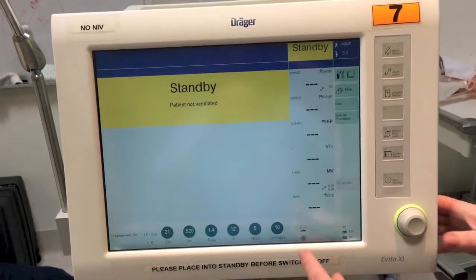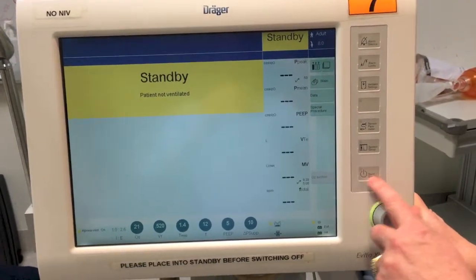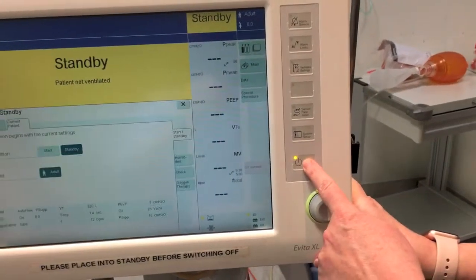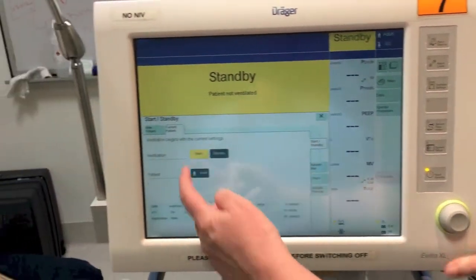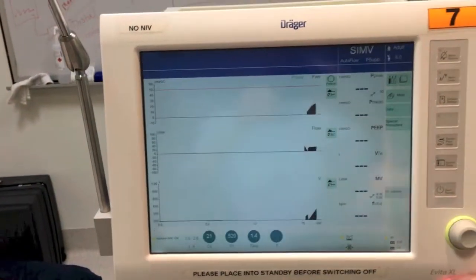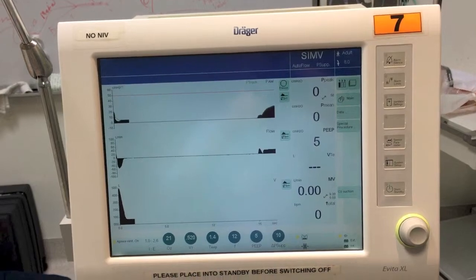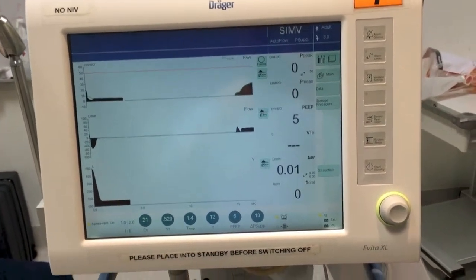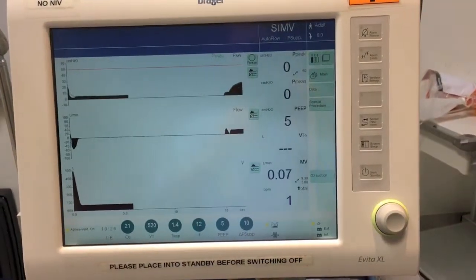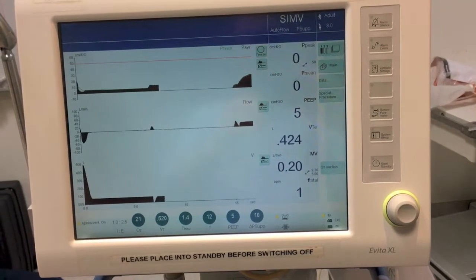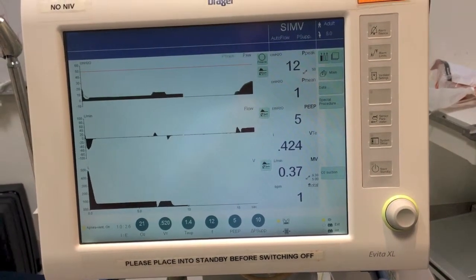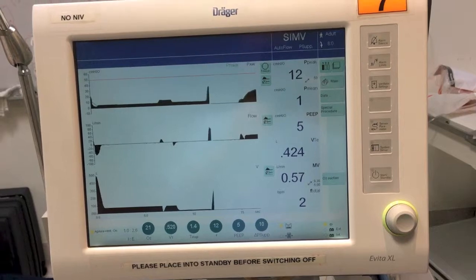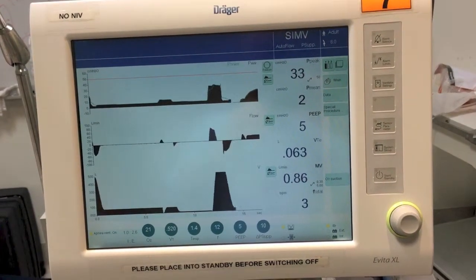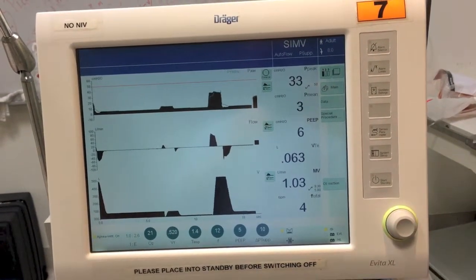So I'll close that now, and then we're going to take it out of standby. The standby button is just on the bottom here, and then we click start, click to confirm, and then your ventilator is auto cycling. It's attached to the test lung, which is just below the ventilator here, and you check that the ventilator circuit delivers the correct tidal volumes. If it didn't, it possibly could have a leak in the system, so you need to check and make sure there's no gas escaping throughout the system.